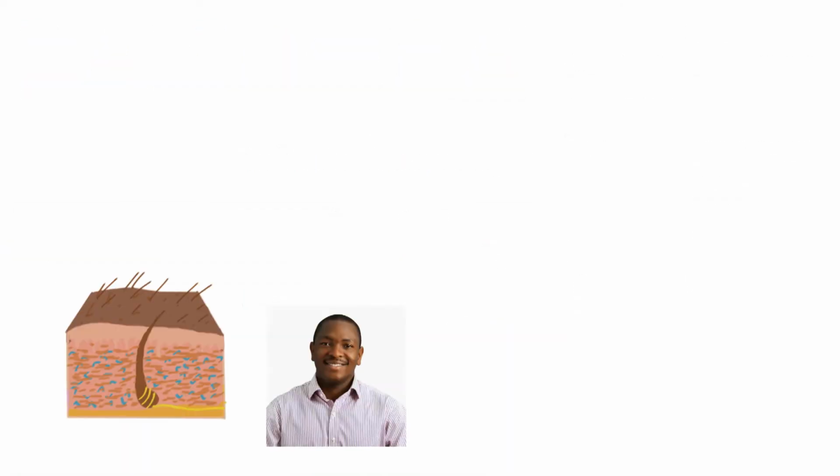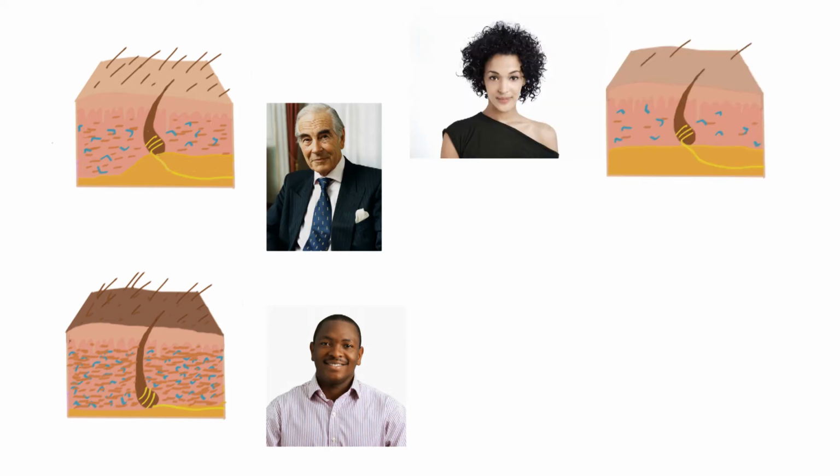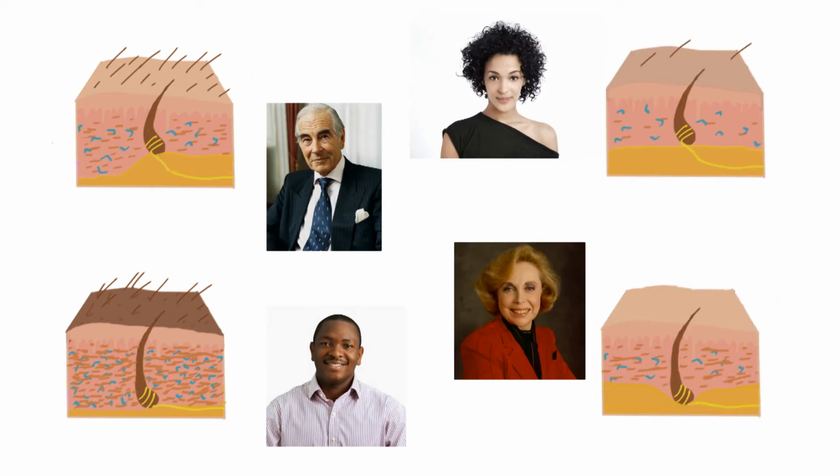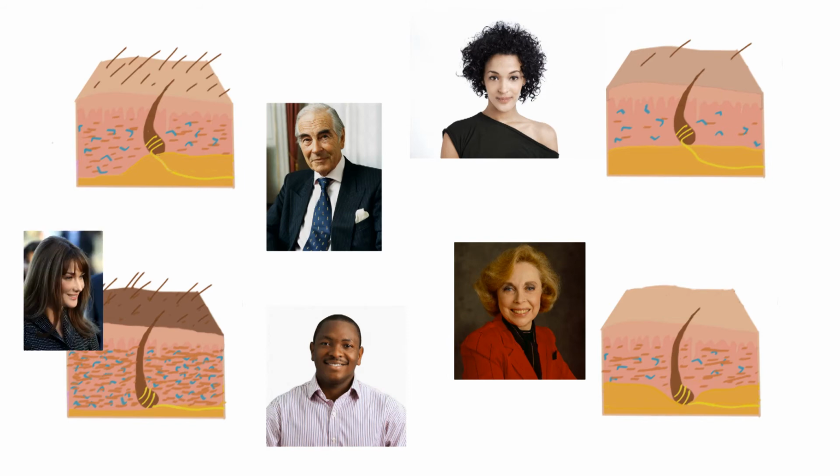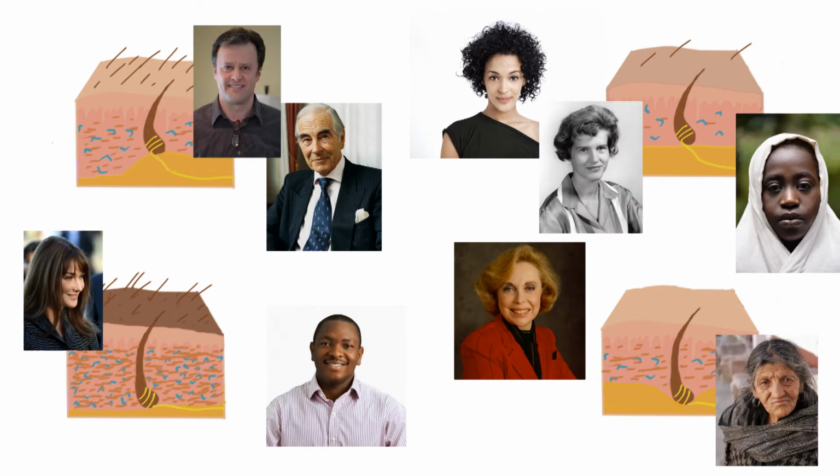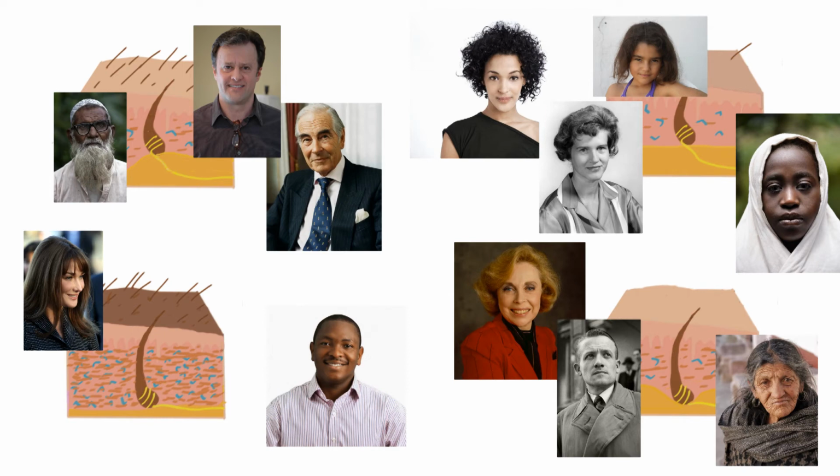For the purpose of non-invasive glucose measurement, the goal is to identify individuals, or to cluster individuals, that have similar tissue characteristics from a glucose measurement perspective. As mentioned before, Medici has combined concepts from handwriting, speech, and song recognition, as well as population segmentation techniques, to create an effective method for resolving our problem. In a more scientifically rigorous fashion, Medici seeks to identify individuals that have the same tissue characteristics from a path-length distribution perspective. Over the past 3 years, Medici has pursued many approaches and encountered numerous dead ends.